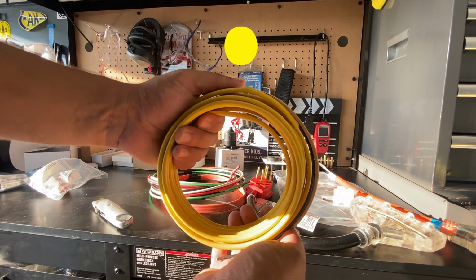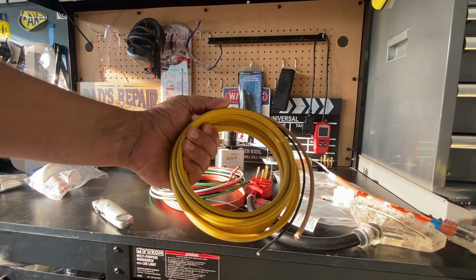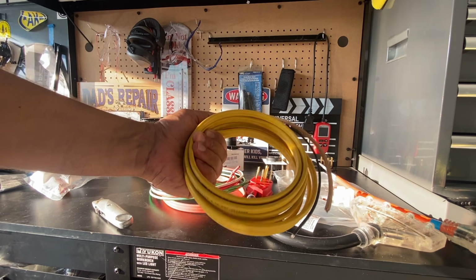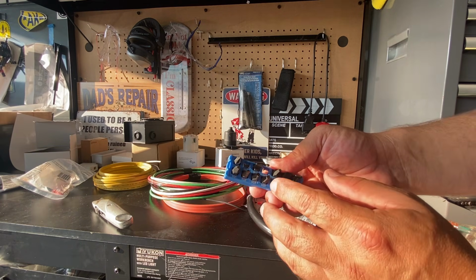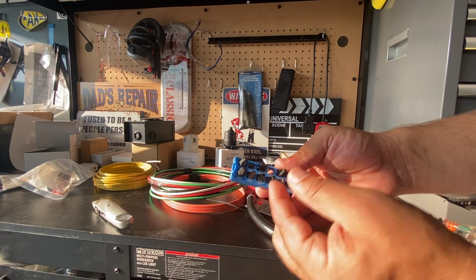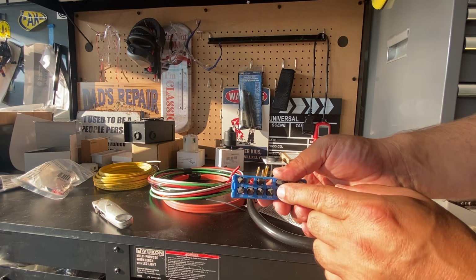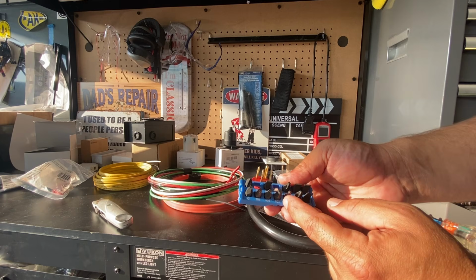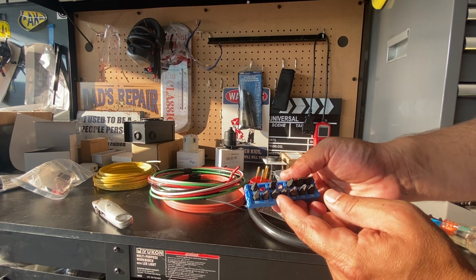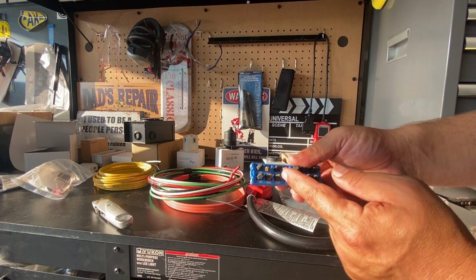For the 15 amp circuits, this wire right here will do. You can use 12-2 or 10-2 wire. Whenever you're working with electrical breakers, those Phillips looking screws are not Phillips, they're actually squares. Most of the time they use a square 2 or square 1, and these will not strip.